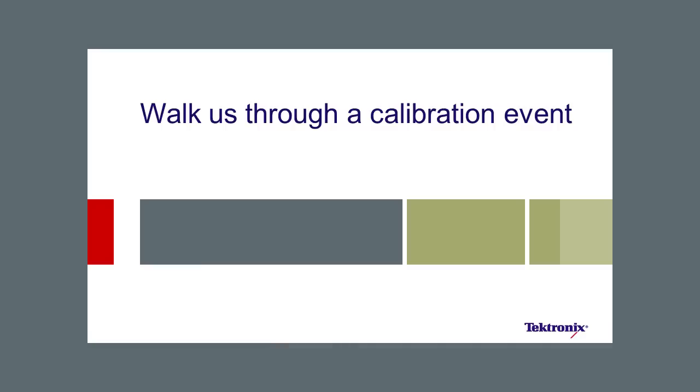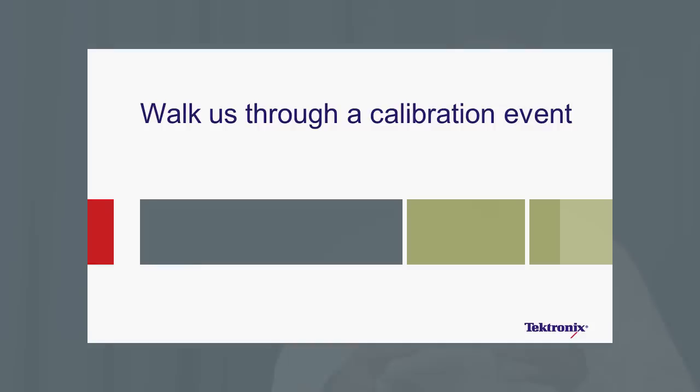As we talk about calibration, a calibration event actually will consist of several things. First and foremost, you need to have the device that you're testing and understand what the requirements or characteristics of that device are. So you need to understand what the requirements for test are. At that time, you also need to identify what standards or references you have to have to properly test the device.